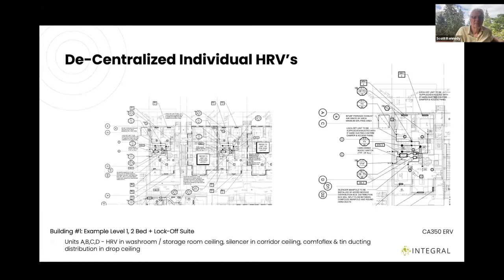Here's an example of how we plan the HRV layouts for Building One — the stacked apartments. Showing the level one two-bed lock-off suite: the HRV is in the washroom, with a silencer just outside in the corridor with a drop ceiling, and ComfoFlex pipes distributing from the silencer boxes to the rest of the suite. The lock-off suite adds complication — we have to run tin ducting from the silencer into that suite because we need a fire damper on it, and there are code questions around smoke dampers.